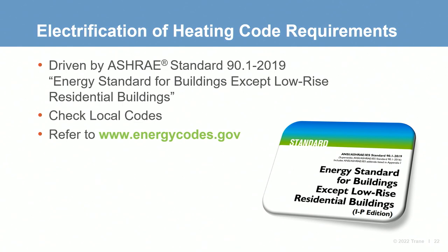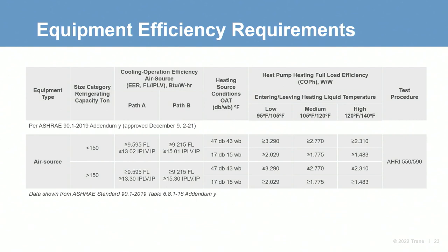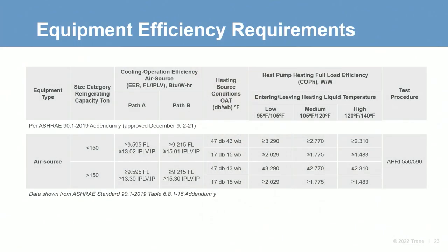Beginning in the 2019 version of ASHRAE 90.1, a new class of equipment was included, heat pump and heat recovery chiller packages. Minimum efficiency requirements are now established and are defined for air-to-water heat pumps. Let's take a further look at some of the aspects of these requirements. First, we see that equipment sizes are grouped into two buckets, less than 150 tons and 150 tons and higher. Next is likely familiar to us chiller folks, and that is definitions for two possible ways to meeting cooling efficiency requirements, defined by path A and a path B, of which one path must be met if the heat pump will be used in cooling mode.